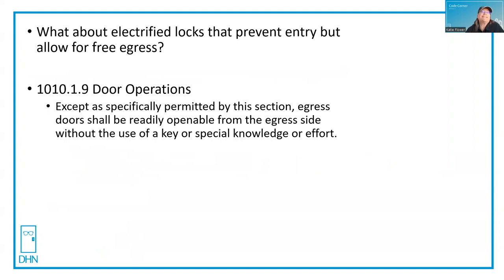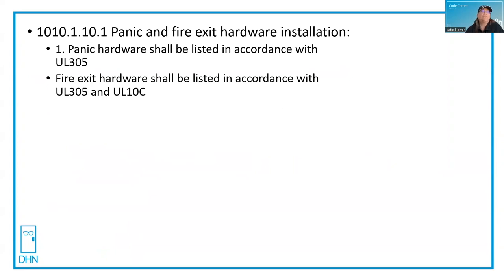Another example of a reference standard is under panic hardware and fire exit hardware, section 1010.1.10.1. Panic hardware shall be listed in accordance with UL 305, whereas fire exit hardware shall be listed in accordance with UL 305 for panic as well as UL 10C, which is the test standard for fire doors. You don't find UL 305 referenced under the lock set section. And if an AHJ asked you for documentation of a cylindrical lock listed to UL 305, you wouldn't find anybody that makes it — because UL 305 is the standard for panic hardware. So unless a standard is referenced by the code, it does not apply.